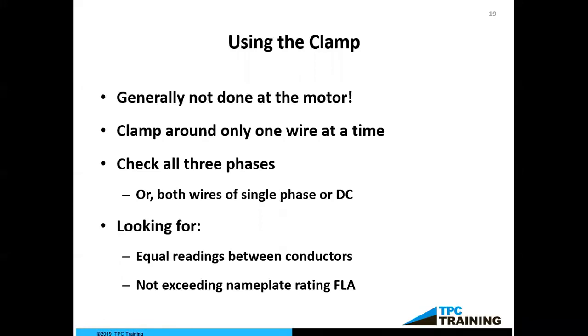And so by putting my amp clamp around each phase, first phase A, then phase B, then phase C, if we take the motor that we had the nameplate on and we're at the higher voltage, when I go around phase A, I should see 61 amps. And then when I go around phase B, I better see 61 amps again, and then 61 amps around phase C. And that tells me a lot.